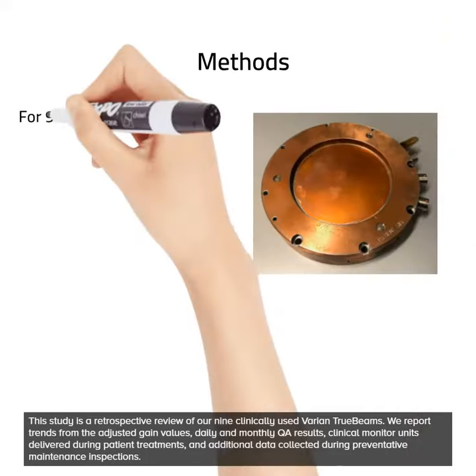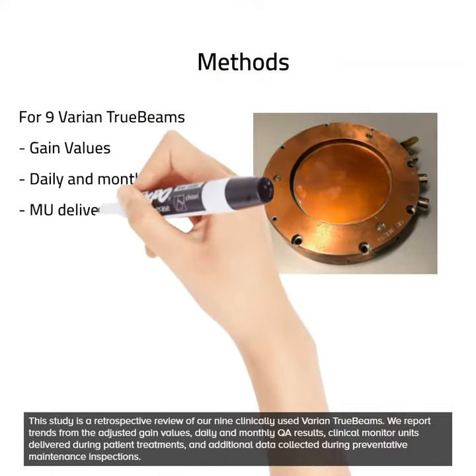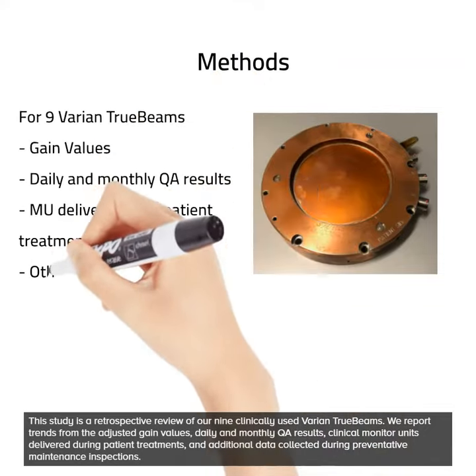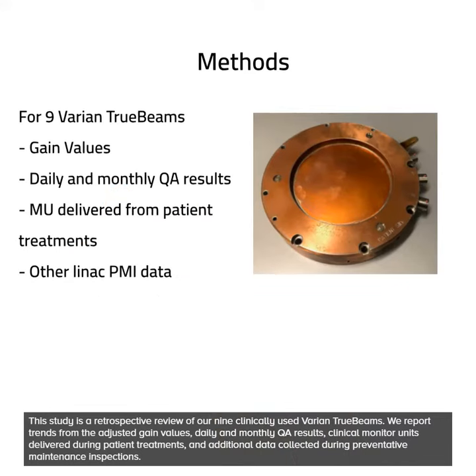This study is a retrospective review of our nine clinically used Varian TrueBeams. We report trends from the adjusted gain values, daily and monthly QA results, clinical monitor units delivered during patient treatments, and additional data collected during preventative maintenance inspections.